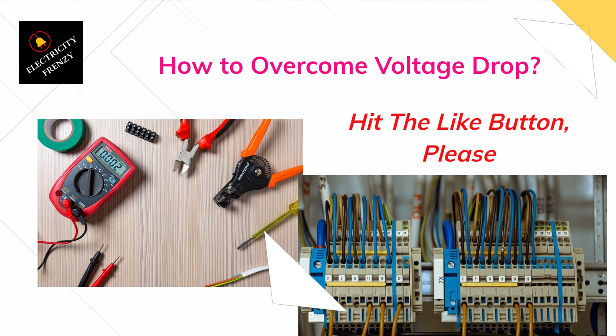How to overcome voltage drop? There are several ways to overcome voltage drop in your electrical system, including: 1. Use larger wire size. Using larger wire size with lower resistance can help to reduce the resistance in your electrical circuit and prevent voltage drop. This is especially important for long wire runs or circuits with high current loads.